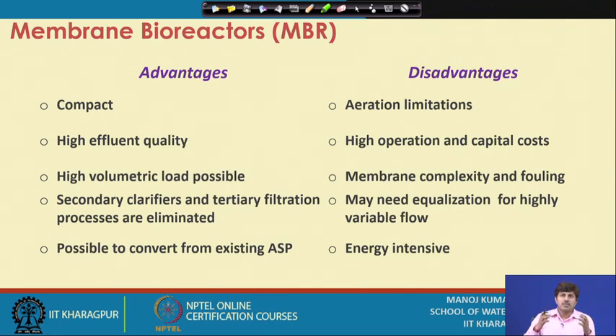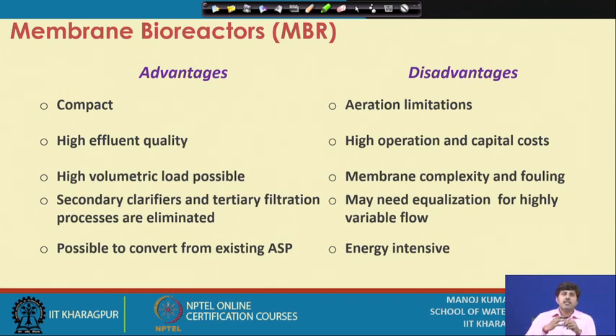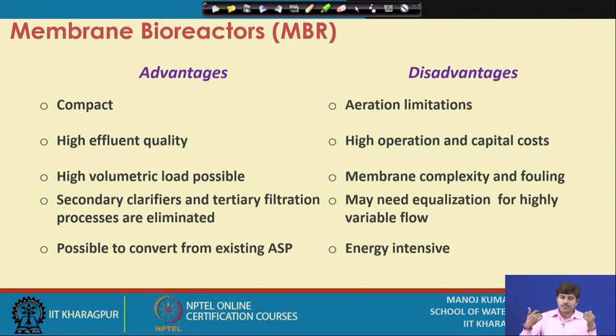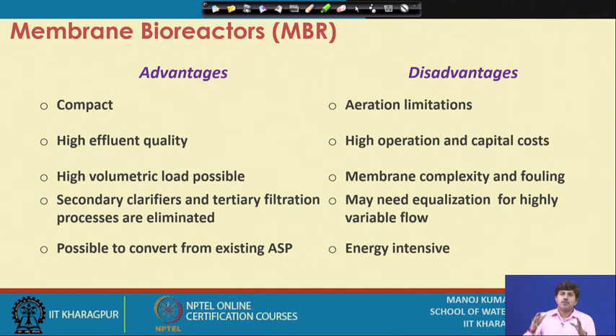The advantages of membrane systems include being quite compact — there is no need for a secondary settling tank or a sludge recycling mechanism, so the area requirement is low. Because there is a lot of biomass in the system, a high organic loading rate can be applied to the aeration system, so the system can withstand high organic loading and a compact system can be designed for the same flow.